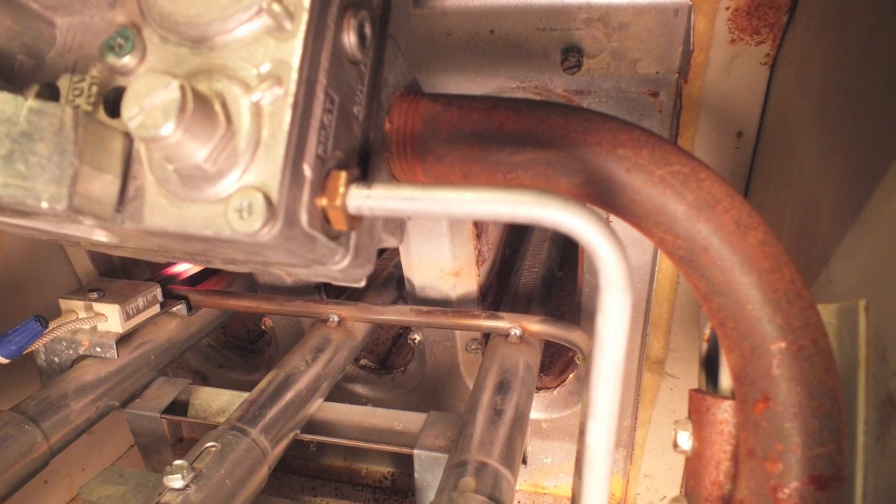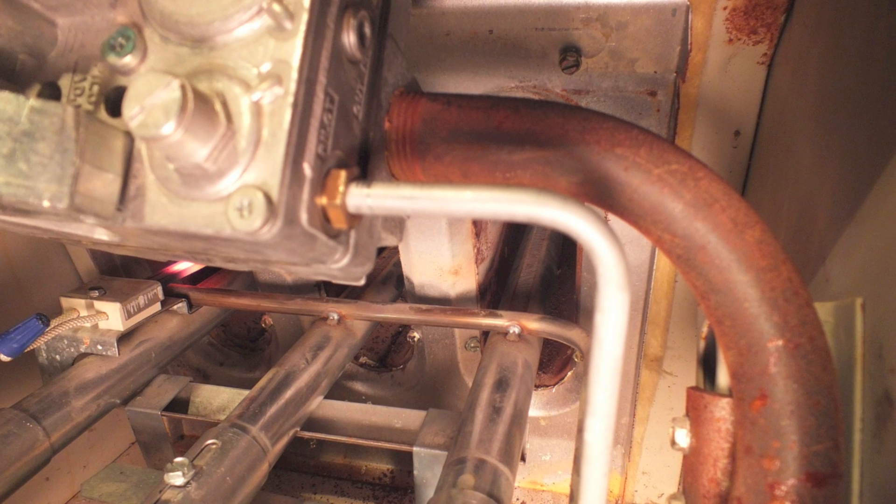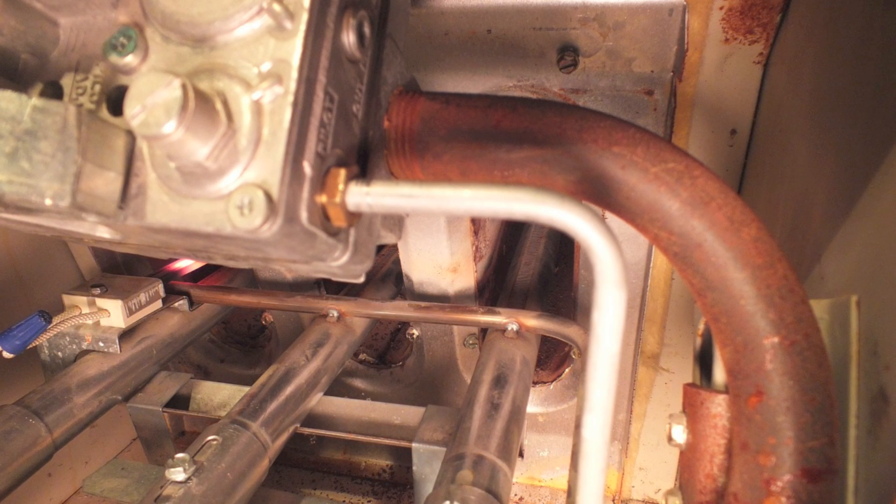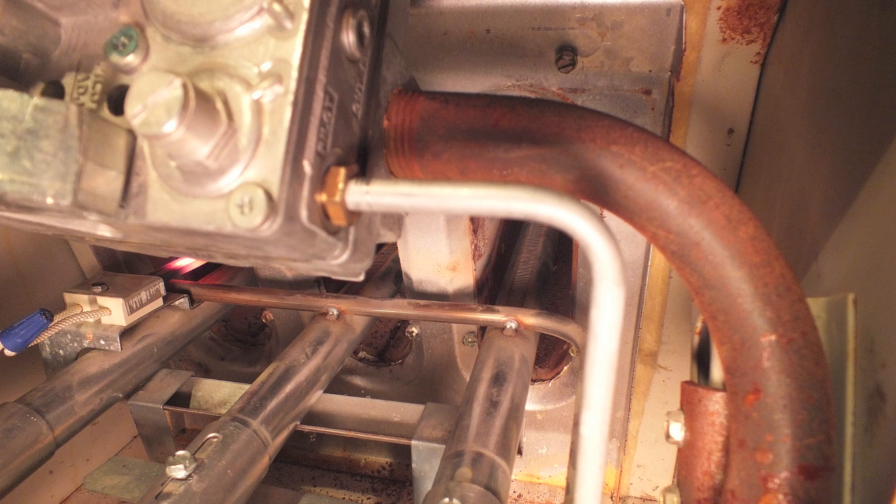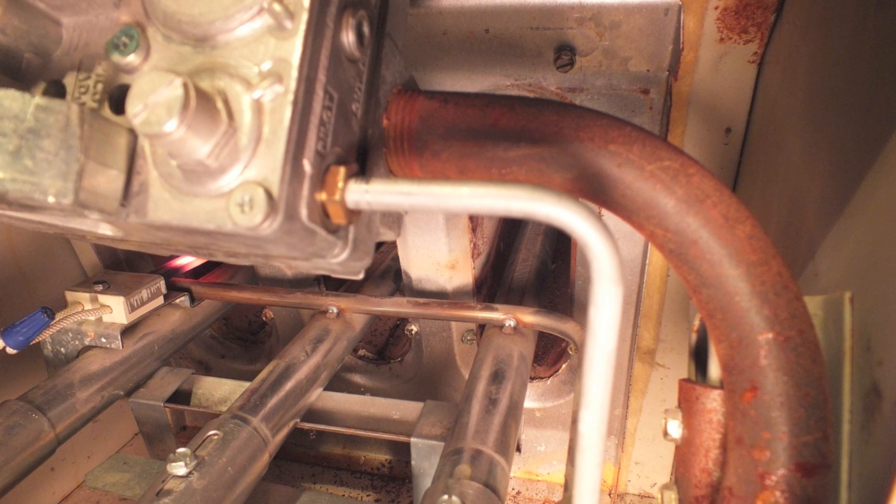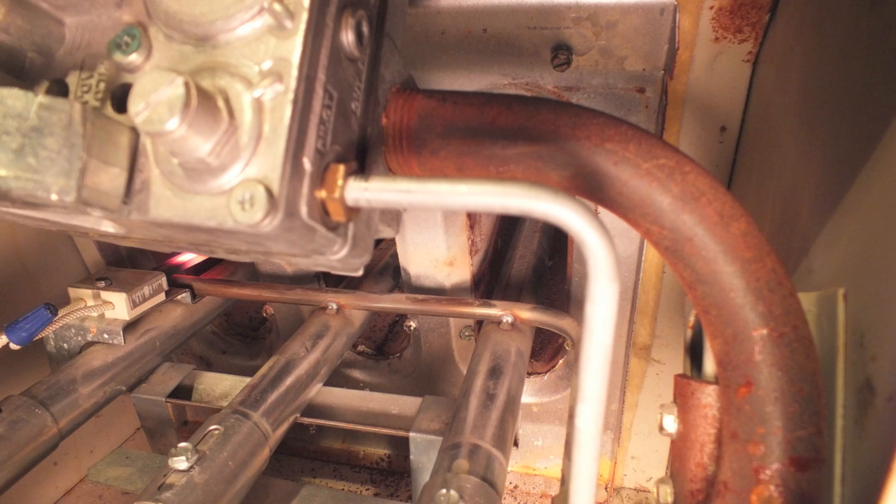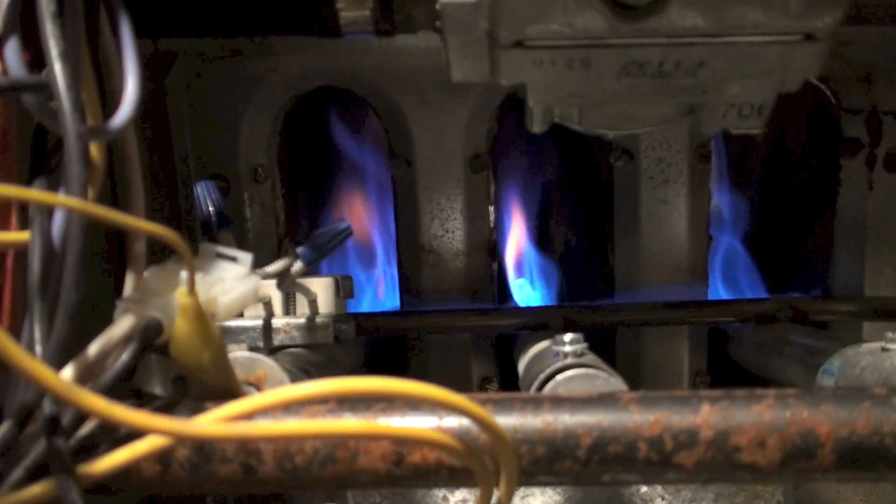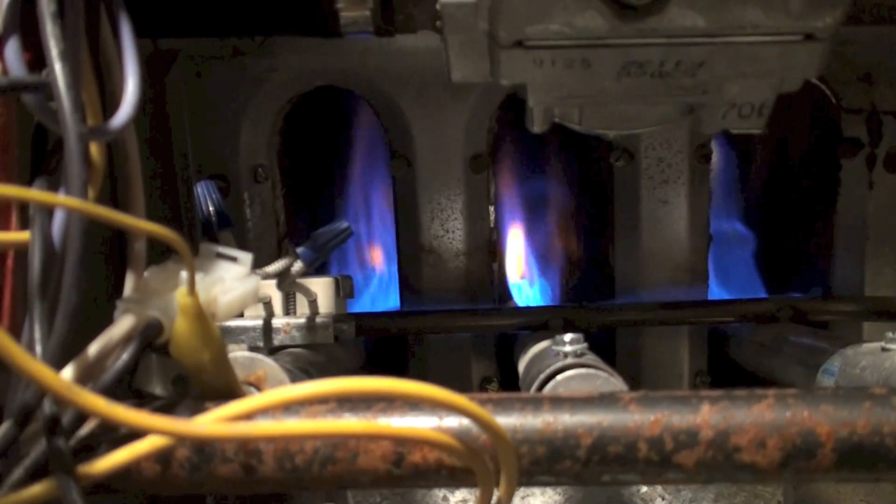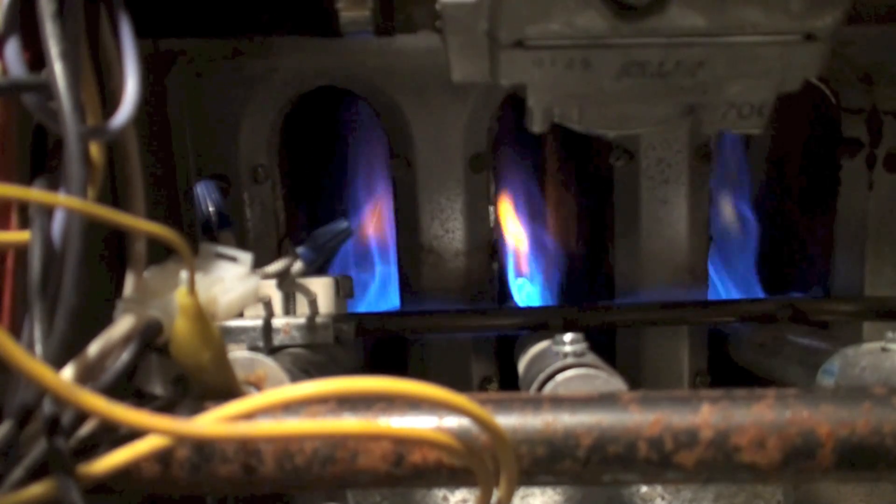And before we're done, remember this part with that little fitting that went into the gas valve, be sure you leak check that, either electronically or you can use soap bubbles. But be sure you leak check that before you're done. And that's pretty much burner clean and service of the RGDA.